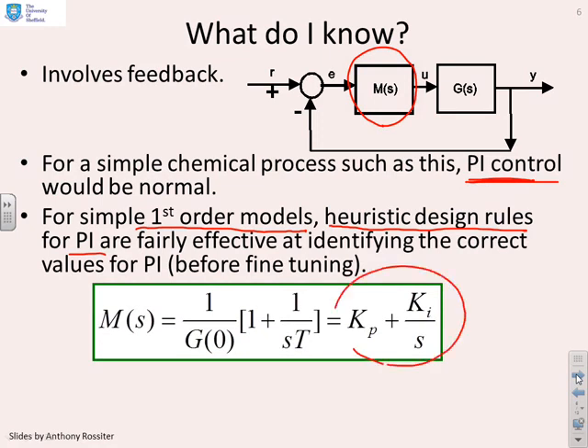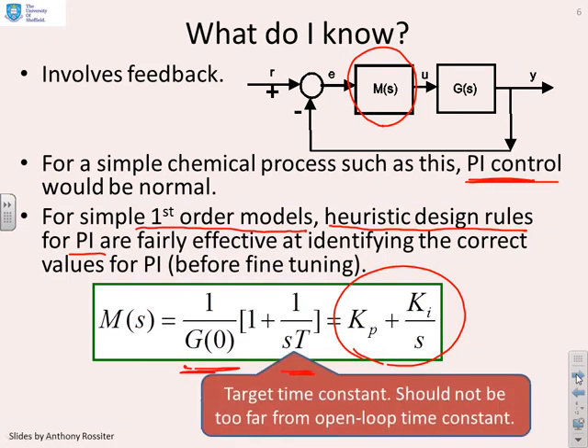Here are the heuristic rules. Basically if we call the PI controller Kp + Ki/s, then we find a Kp of 1/G(0) plus a Ki of 1/(G(0)×T) is pretty much what you want, and that will give you reasonable performance. There is a bit of a caveat - these rules work well if the target time constant is not too far from the open loop time constant.